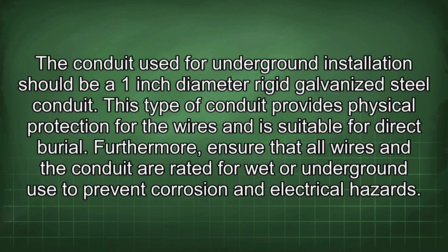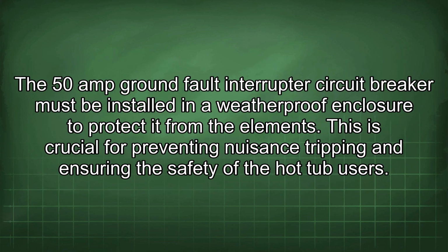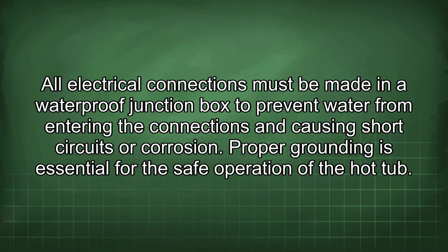Furthermore, ensure that all wires and the conduit are rated for wet or underground use to prevent corrosion and electrical hazards. The 50 amp ground fault interrupter circuit breaker must be installed in a weatherproof enclosure to protect it from the elements. This is crucial for preventing nuisance tripping and ensuring the safety of the hot tub users. All electrical connections must be made in a waterproof junction box to prevent water from entering the connections and causing short circuits or corrosion. Proper grounding is essential for the safe operation of the hot tub.